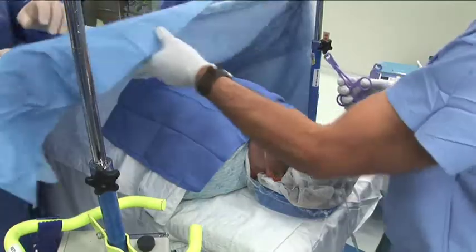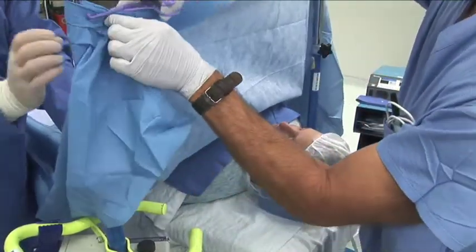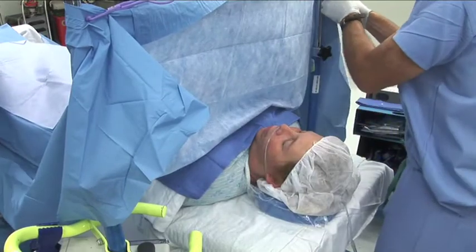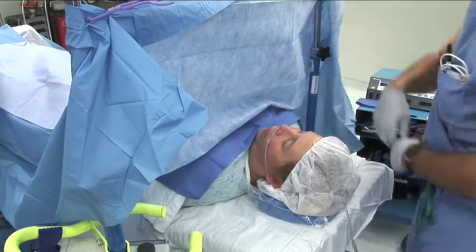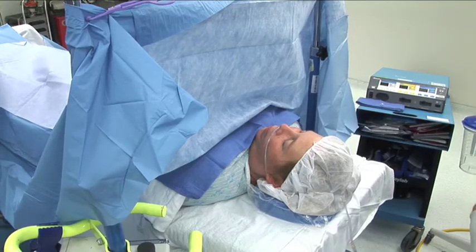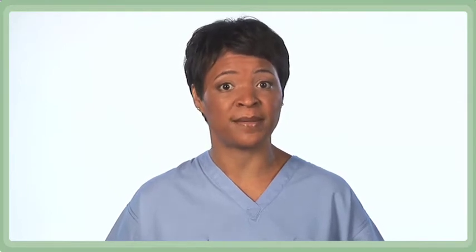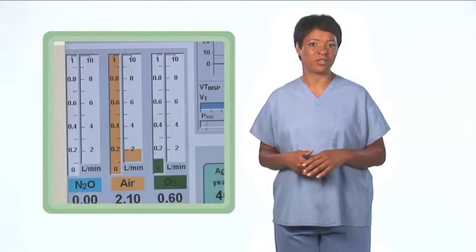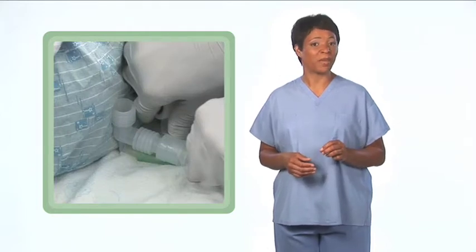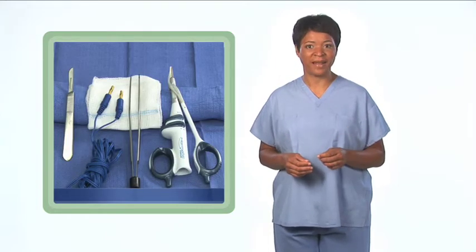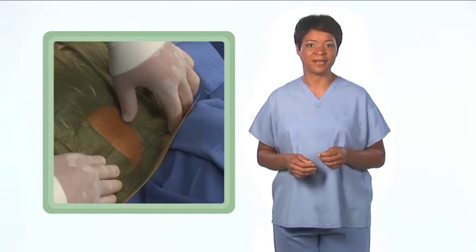Draping techniques, such as open draping, where the face is only partially covered or not covered at all, have been advocated to reduce the risk of oxygen accumulating under the drapes and flowing into the surgical site. Be aware, these techniques should only be used for exceptional cases, since they do not fully eliminate the surgical fire risk when delivering oxygen above 30%. To summarize, the preventative methods that can be used for exceptional cases include blending air and oxygen, diluting the underdrape space with air, using alternative surgical modalities, and using modified draping techniques.